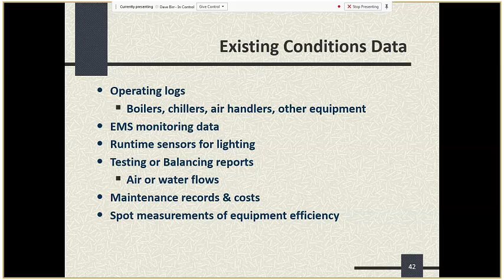Now, I want to get into some of the challenges to calculating an accurate baseline. Baseline analysis might fail to account for periods during which equipment was out of service. How would this be the case? If you're looking over a historical time period and just at utility data, that's nice, but what if some of the equipment was down during that period and you didn't know about it? That would skew your utility consumption profile.